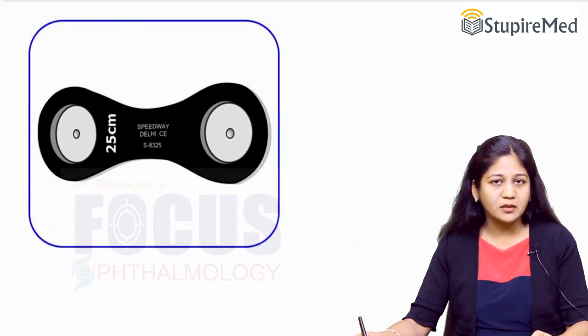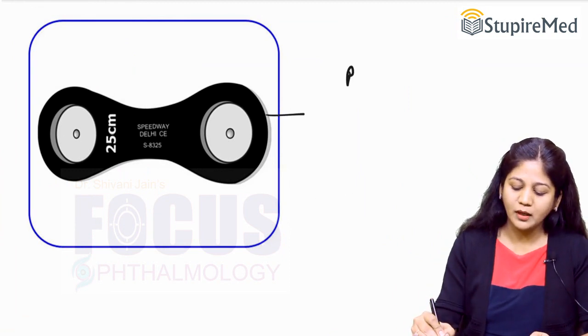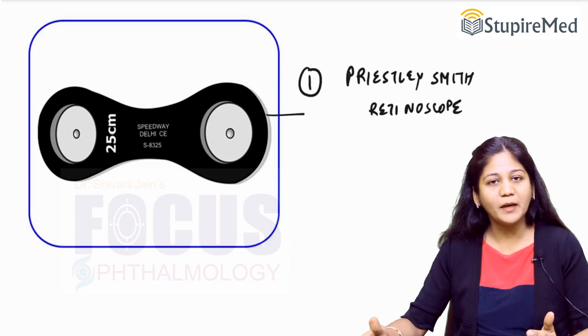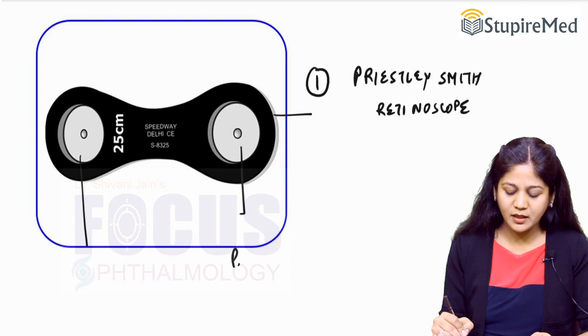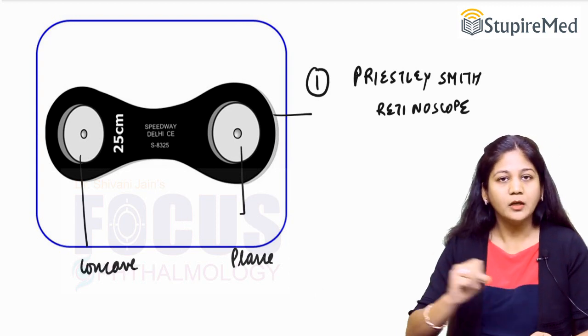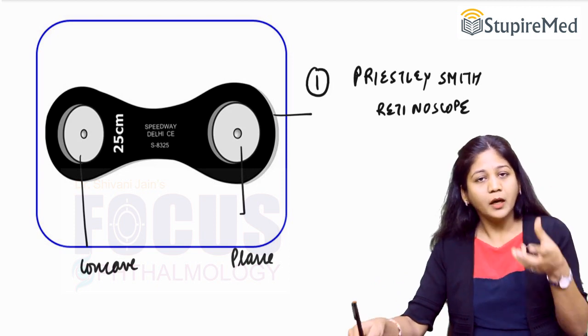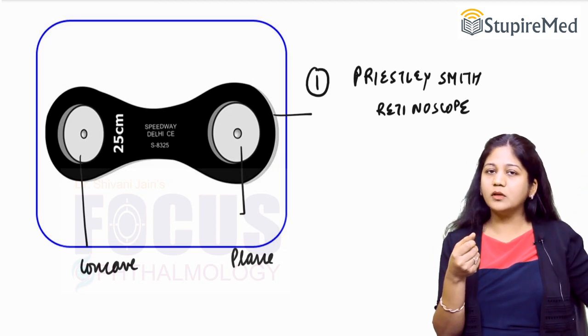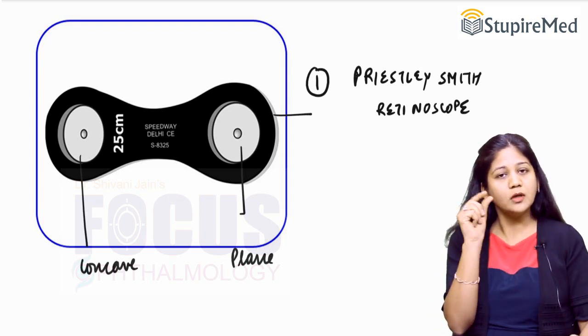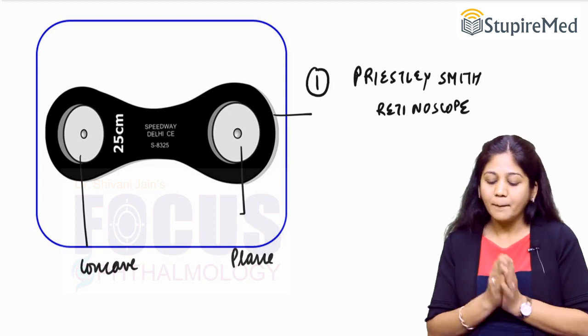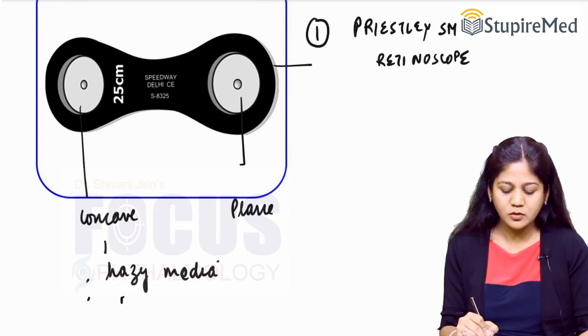Retinoscopy can be done by two types of methods. The first is known as the Priestley Smith retinoscope, which has a plane mirror and a concave mirror as reflecting surfaces, with a small aperture. When we hold the retinoscope in one hand, the source of illumination is behind the left shoulder of the observer. We observe the reflex in the patient's eye through the hole. Most commonly we use the plane mirror; the concave mirror is used when there is a hazy medium or a very high refractive error.